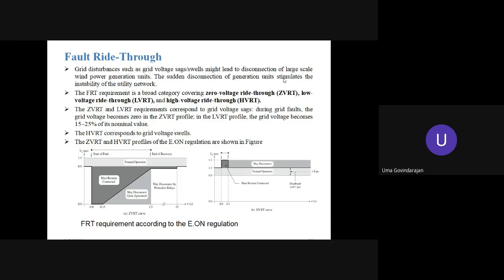According to the international regulation, the zero voltage ride-through and HVRT profiles are shown in the diagram. It may vary from country to country. If you look at this diagram, let us say that at t equal to 0 a fault has been initiated or has occurred. Until then, the grid voltage is 0.9 per unit. A variation from 0.9 to 1.1 is allowed, and that is normal operation, where we can operate normally.